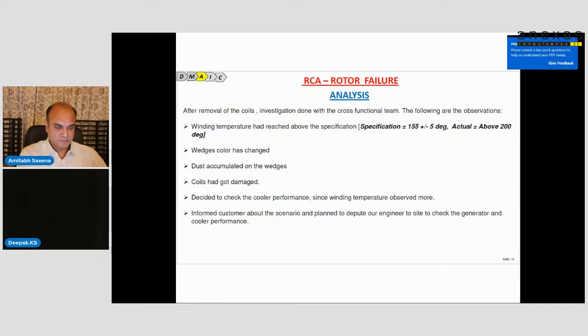Yes, that's one analysis part. The second thing is the wedges' color has changed. Dust accumulated on the wedges. Coils had got damaged. So with this, we wanted to check the cooler performance since the winding temperature was observed to be higher. There is one more part where our supplier supplies the cooler. It is mounted on the top side of the generator. So we informed the customer about the scenario and planned to depute our engineer to site to check the generator and cooler performance.